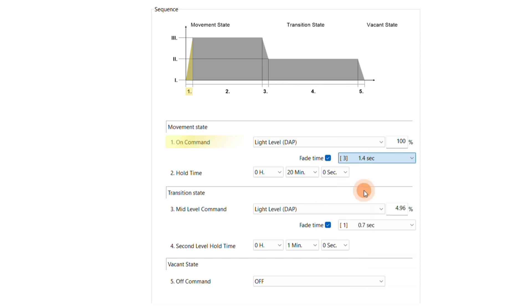Additionally, we will add a fade time of 1.4 seconds to this command. This ensures that the room's illumination does not increase abruptly. With the hold time, we can define how long this light level will be kept. Let's set it to 10 minutes.